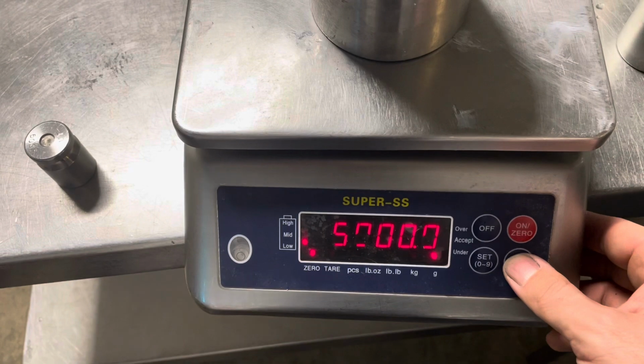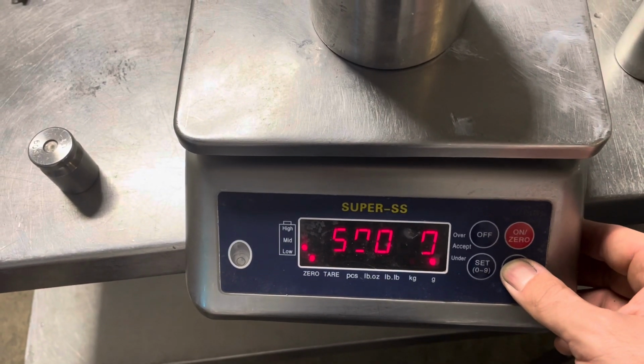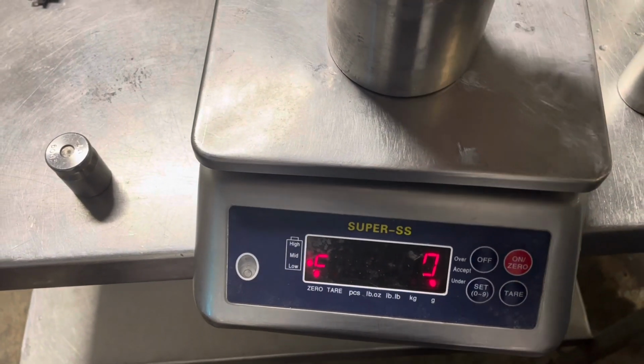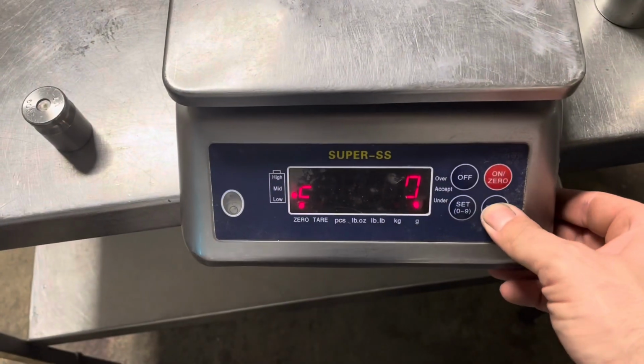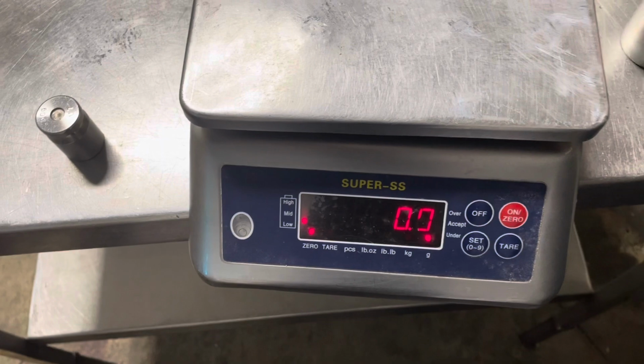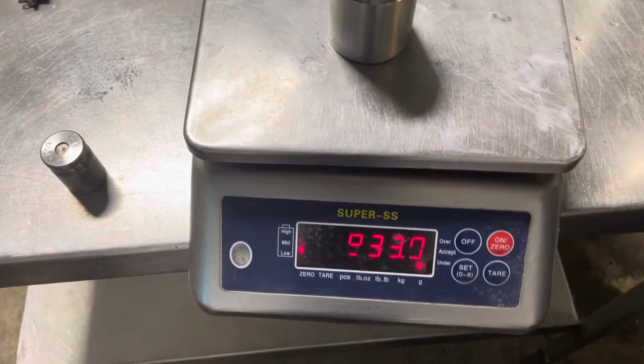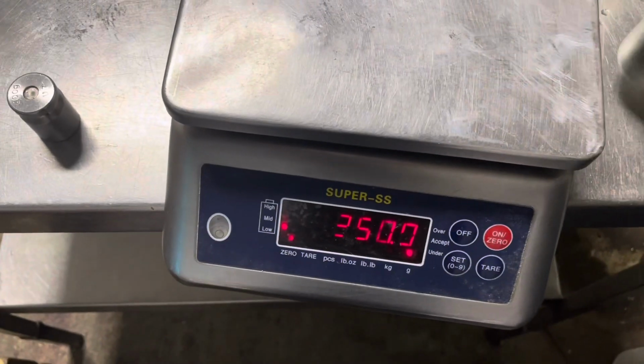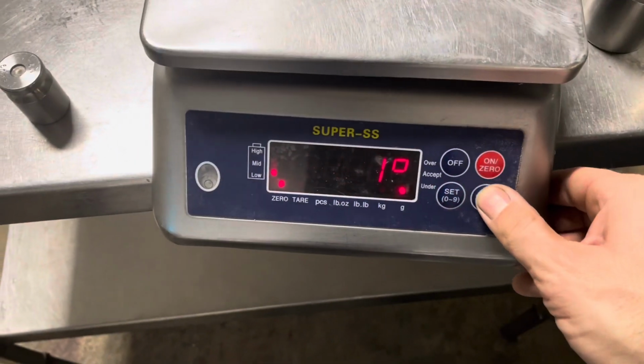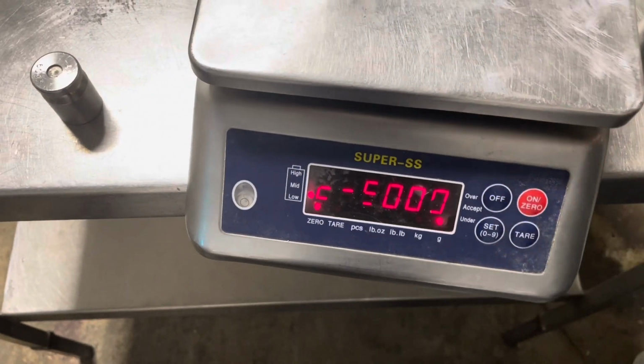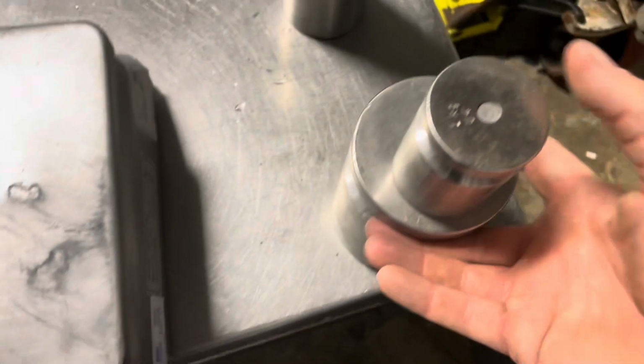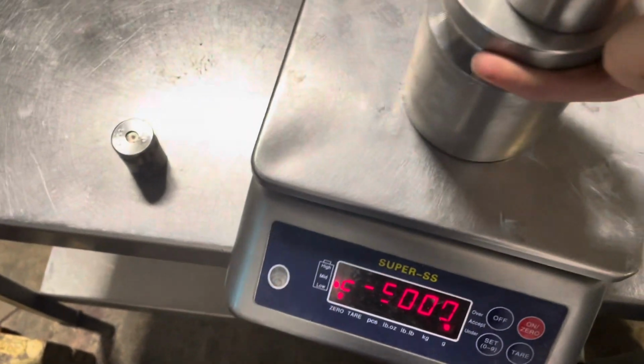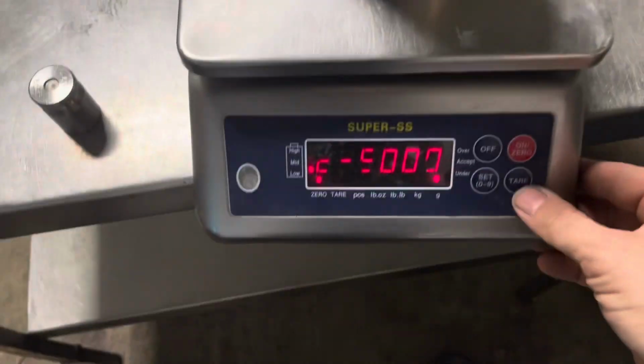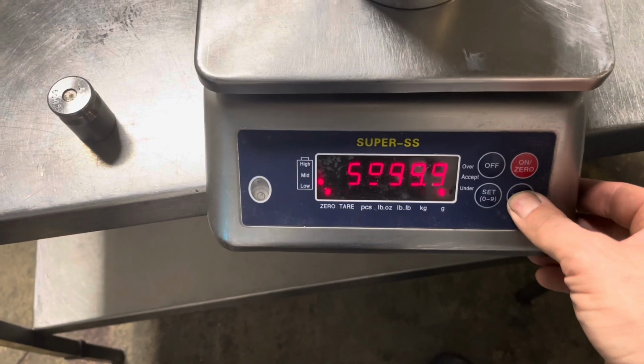But as you can see here, I am having issues with the scale. And when I do a single point calibration, it does not come back as weighing accurate. So now the scale's done, we throw the weight on it, and that's not 1 kg, that's less. That's not good. So now we're going to do a single point calibration again. I'm going to put 6 kgs on the scale and see if that makes a difference. Surprise, surprise, it does not in the end.